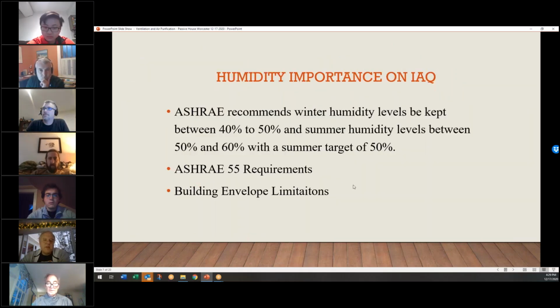Okay, so humidity. We know it's always been kind of an important thing for comfort, but now, again, with COVID-19, it's become more of an interesting thing for air quality. What is the impact of humidity? ASHRAE recommends humidity levels between 40 and 50% in the winter, and in the summer between 50 and 60, with a target of 50%. You don't want to go much over 60 because now you can get into mold and mildew issues, and 40 to 50% is a very high humidity level in the winter for most. I mean, I would recommend 40. That would be my recommendation.